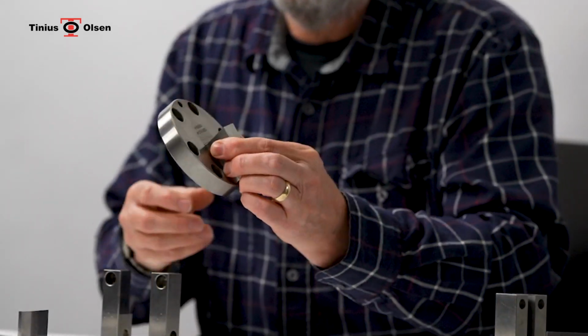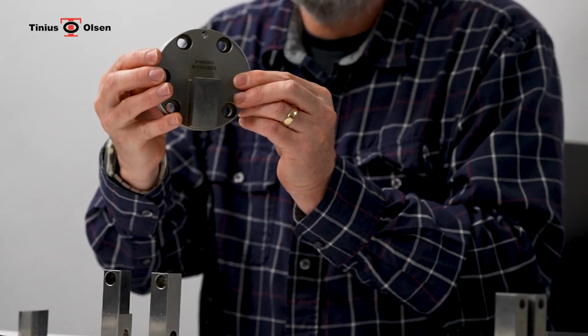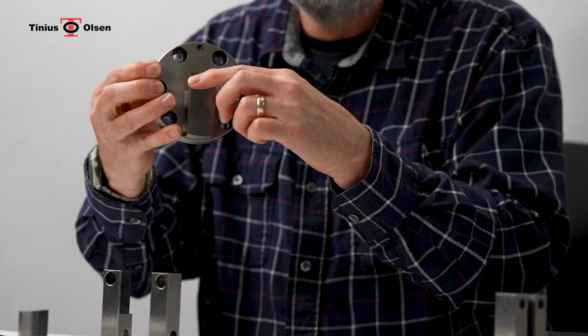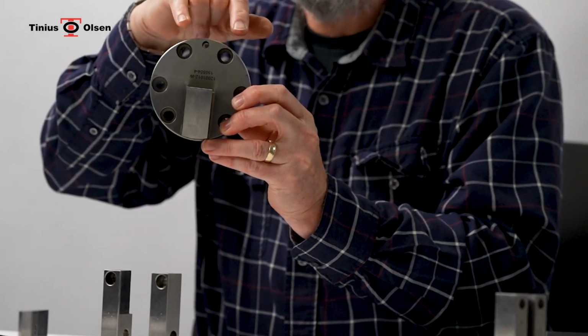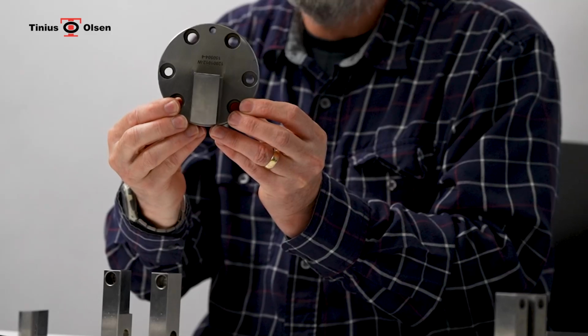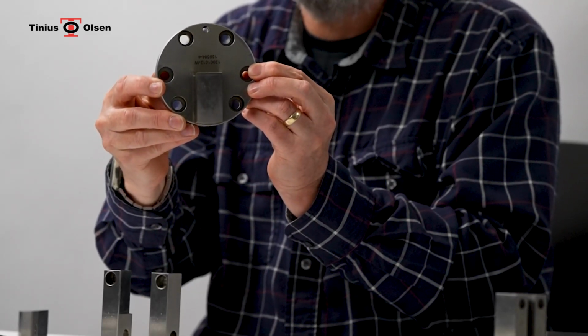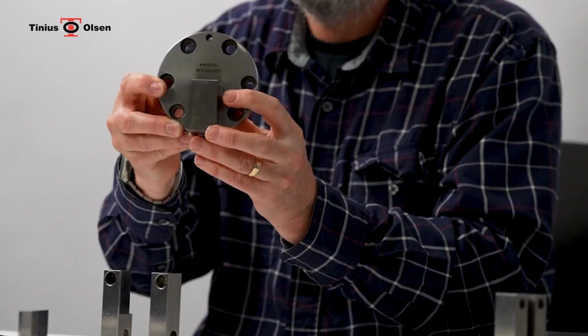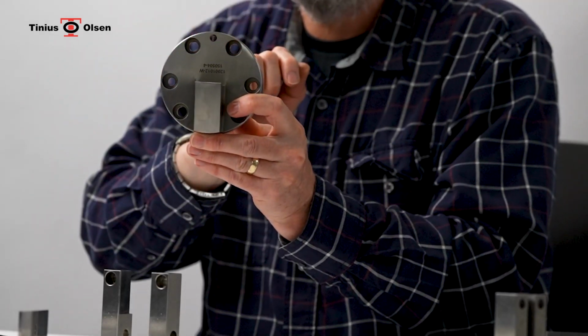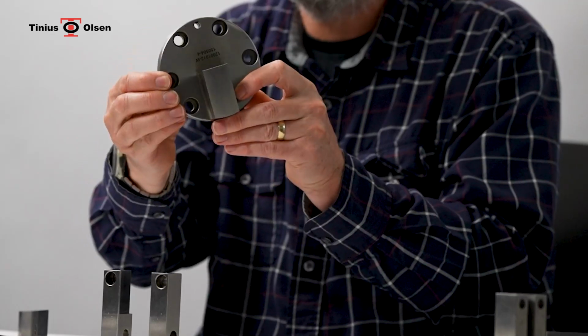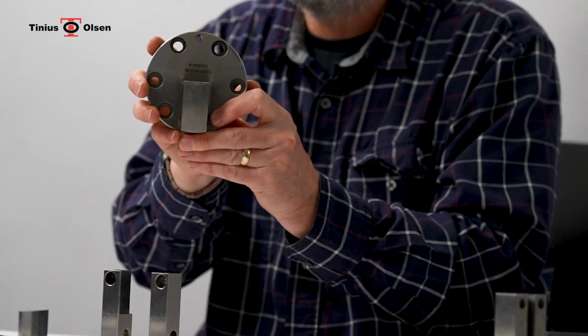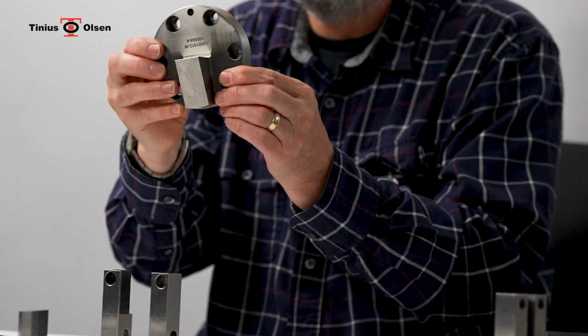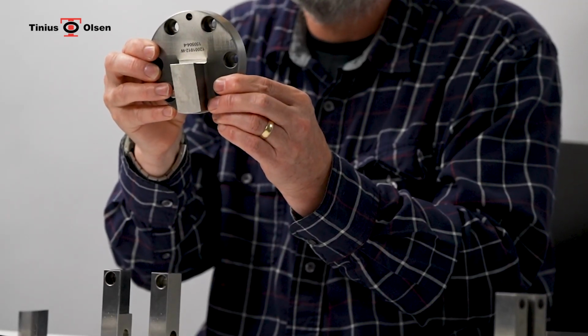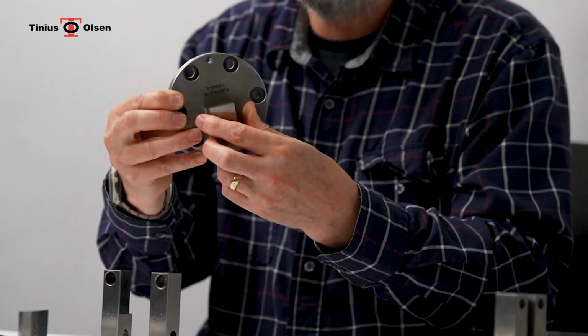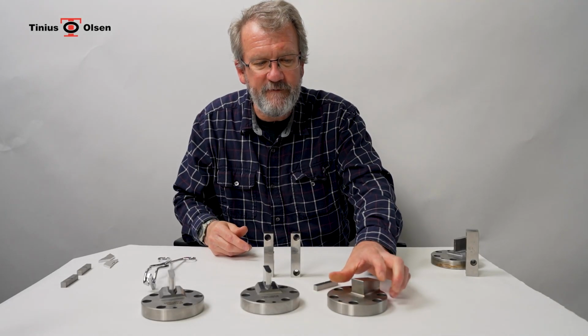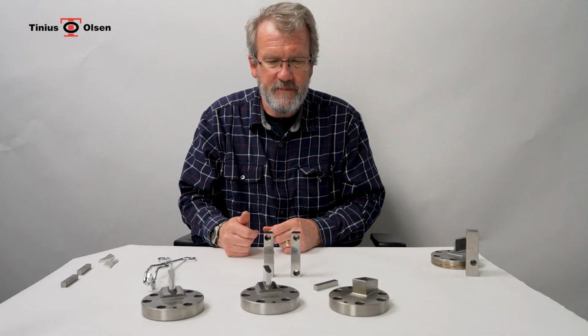The striker for an IZOD is this style of striker with the bull nose on it here. It has 4 mounting locations with the recessed bolt pattern here and 2 jacking points to allow it to be extracted from the hammer. The final location up here, this pin, allows orientation of the striker to be tightly controlled so that you have the striker correctly aligned with the sample. This will fit in a standard metal impact hammer and therefore can be switched out if needed.